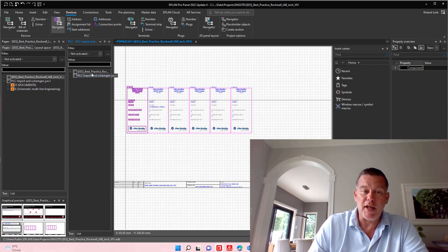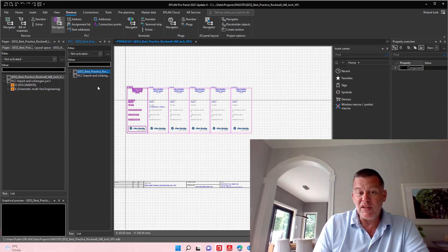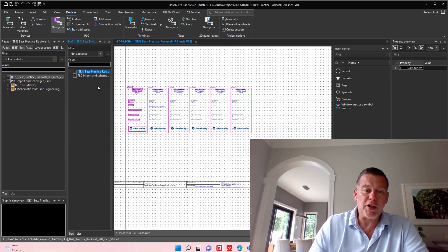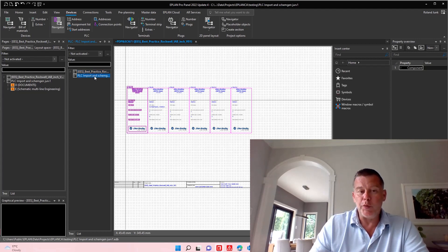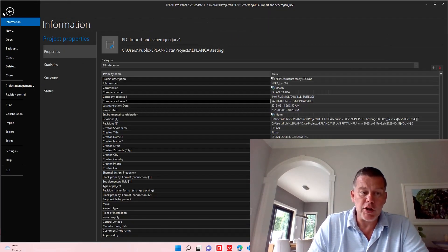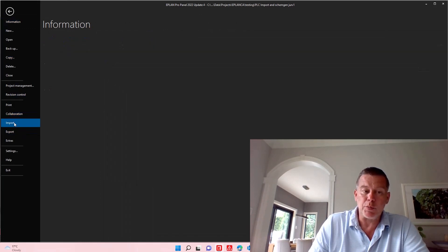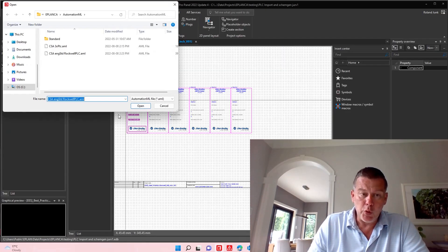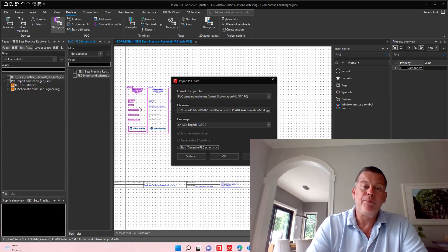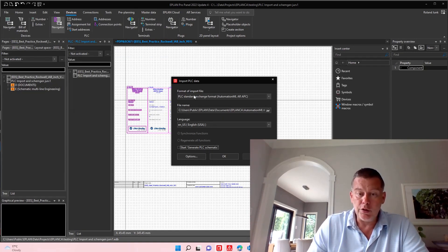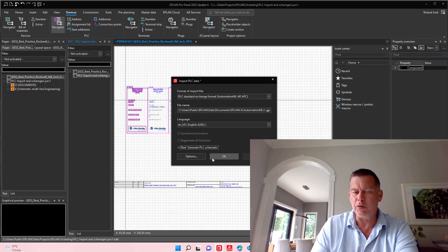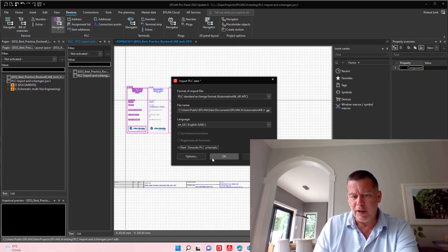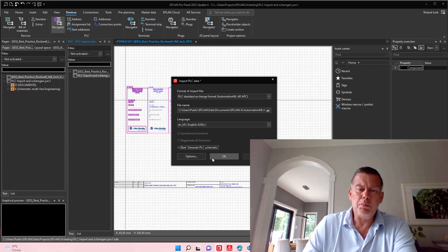All I had to do is export my PLC data either directly from the Rockwell Integrated Architecture Builder or I can do it within this project here and I'll show you how to import it back into this project. So here we have the PLC data import which is this AML file and I can configure this. I can go straight into starting and generating the PLC schematics like the input cards and output cards and what's connected to it.